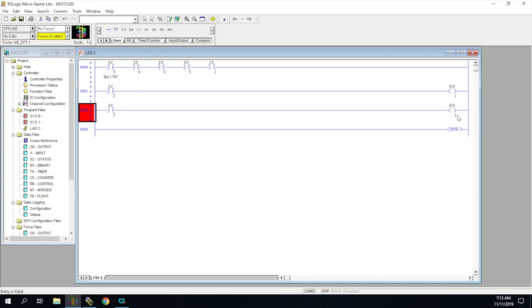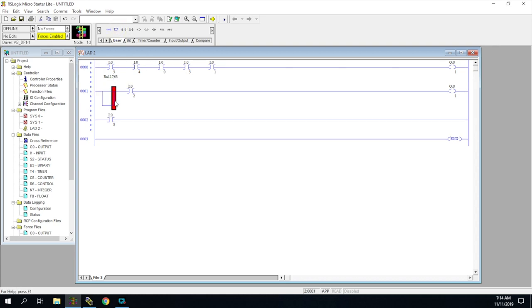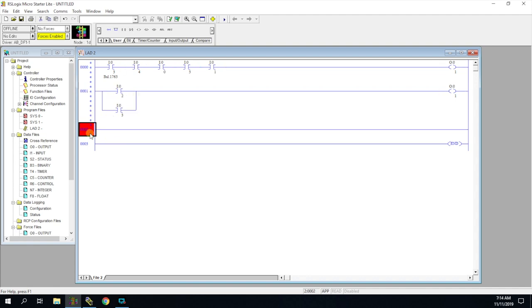So this is the reason we don't do that. We never put more than one output in for one terminal. Let me re-say that. There's only one output address per output. Never do the same output twice. So we're going to take this one, I'm just going to put it back up here later on, and I will re-code it. And this is where the OR circuits come in. So we can go ahead and we can throw this thing together, and we now have an OR circuit.